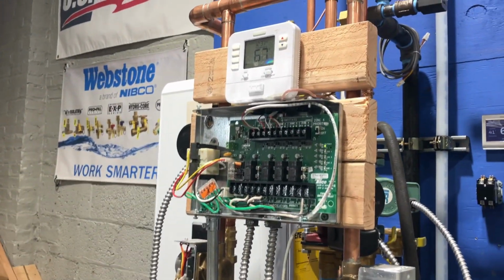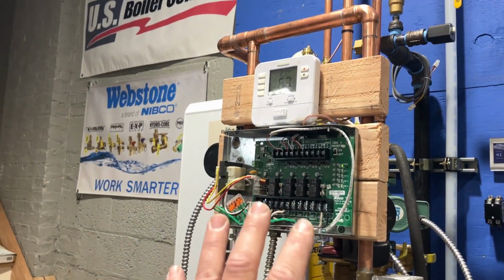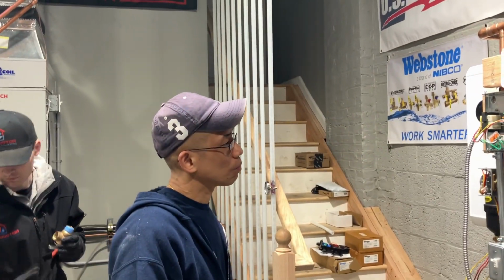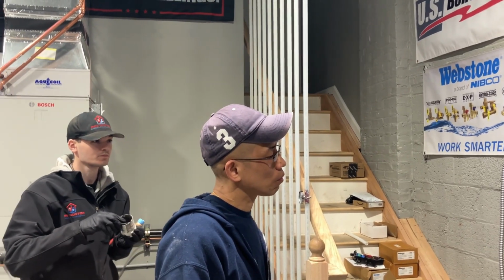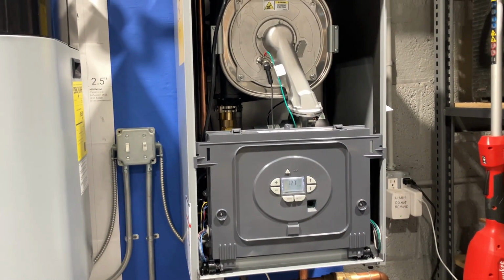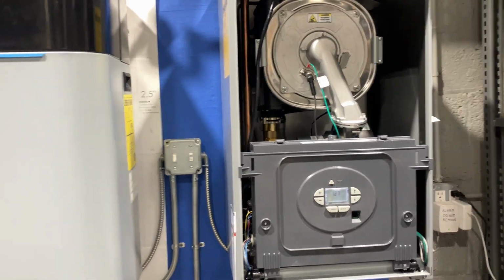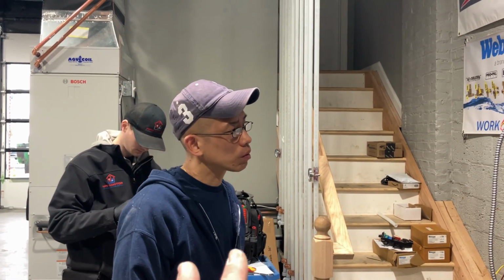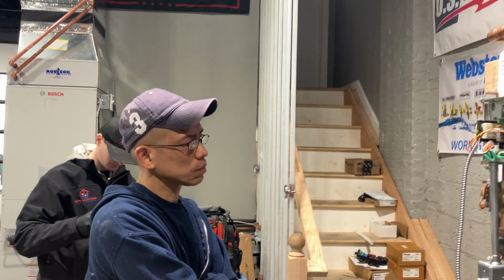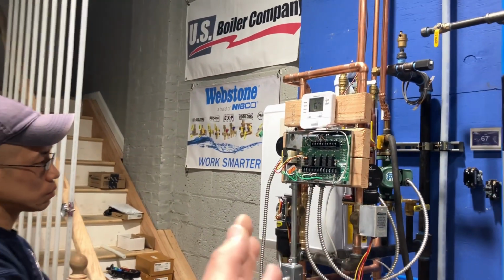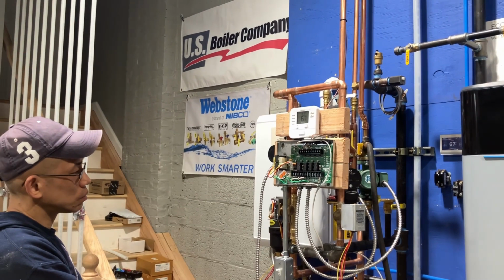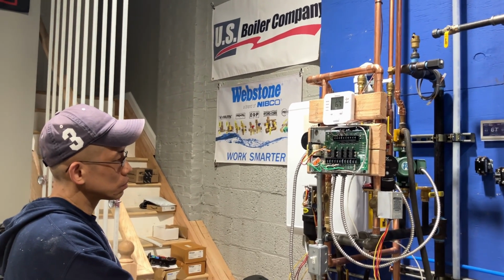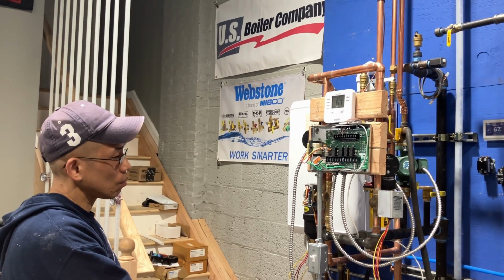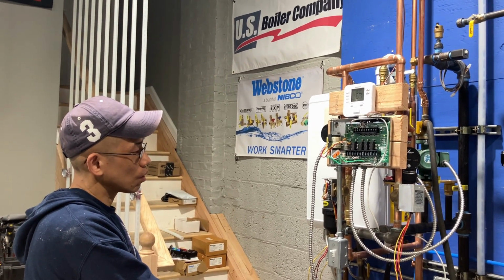Now we're going to duplicate a failure. All right, so our switching relay is installed. You now are at a service call for no heat out of your newly installed boiler, which is this Burnham Alta by US Boiler. Okay? No heat. They have hot water, but they don't have heat. You just pulled up to the service call. I want you to troubleshoot. If you don't know something, take no more than 5 seconds before you say you don't know, for time purposes, okay? Okay. Go.